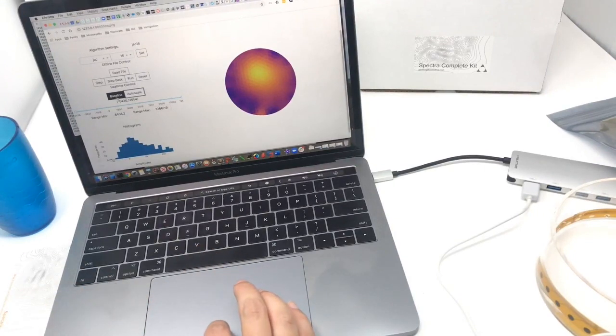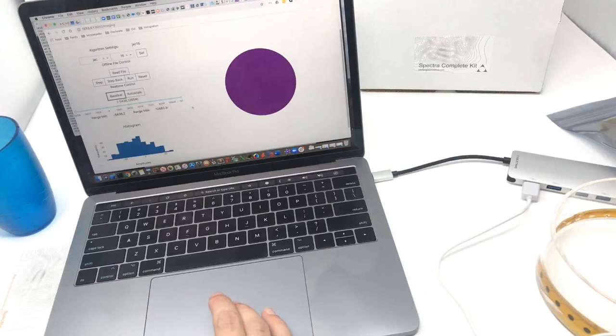So now we are imaging, but we haven't put anything in the tank, it's empty. I'm just going to baseline it. Should change the image, and it also changes the scale of amplitude in the image reconstruction to plus or minus 50 image reconstructed units. That will allow us to see a better contrast when we put an object into the tank. So baselining is quite important because it scales the numbers to a common reference.